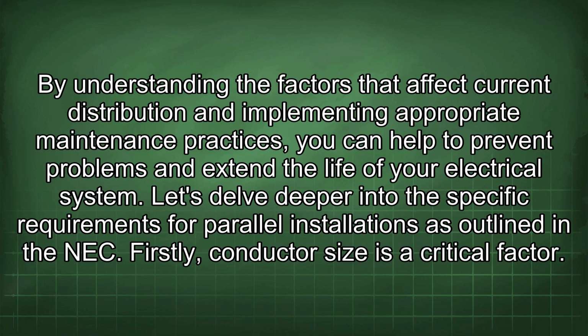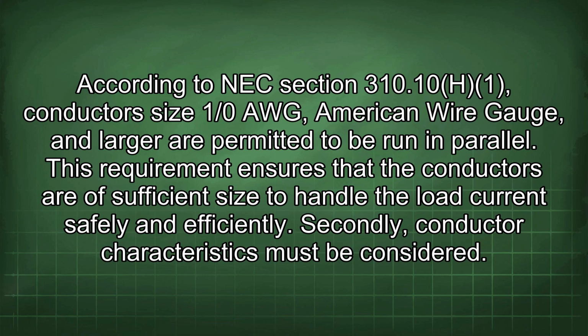Let's delve deeper into the specific requirements for parallel installations as outlined in the NEC. Firstly, conductor size is a critical factor. According to NEC Section 310.10, only conductors size 1/0 AWG, American Wire Gauge, and larger are permitted to be run in parallel. This requirement ensures that the conductors are of sufficient size to handle the load current safely and efficiently.